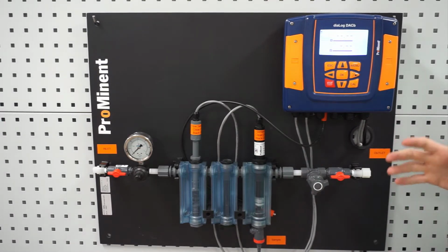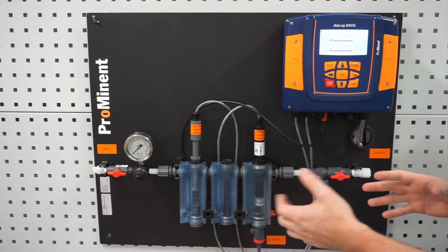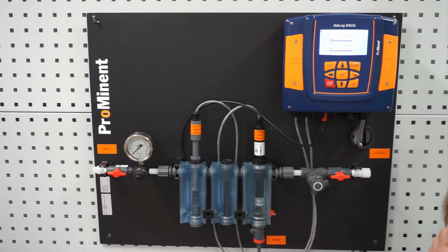We'll start off by going through the process of getting our flow set up correctly and then also preparing our sensors to read correctly. Then we will go into the controller and I'll walk you through showing you what wiring we have done from the factory and then show you what options are in there to allow you to, in the field, add additional components. From there we'll go into the controller, we'll push some buttons, I'll walk you through all the menus to show you exactly what we programmed from the factory and then show you other options that are in there. And then lastly, we will do a calibration of our sensors so that they can be up and running accurately.